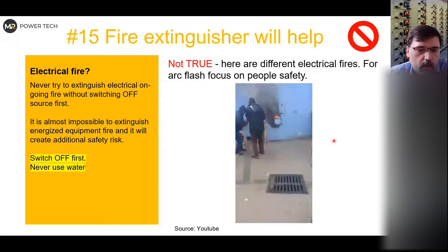Otherwise, it's impossible to do. And just to show you an example, that's how it looks. So you see the arc flash happening, it's not a big one, and you think you can put it down. So they will try. I think it's CO2 or powder. And you see that it keeps going. It's not disappearing, because we still have power, we still have voltage, and we still have a source of energy for the arc flash to happen.